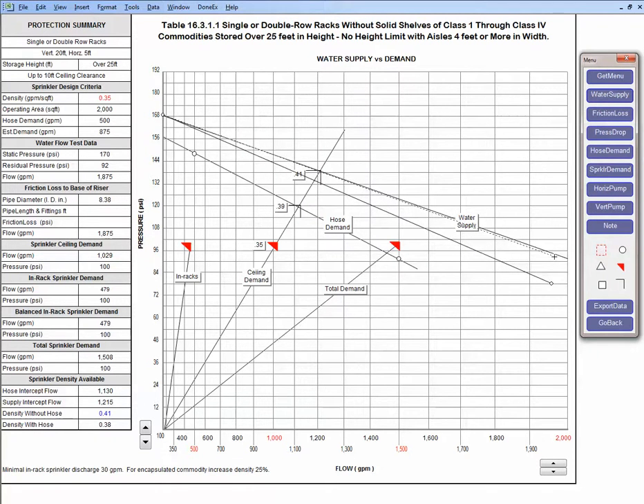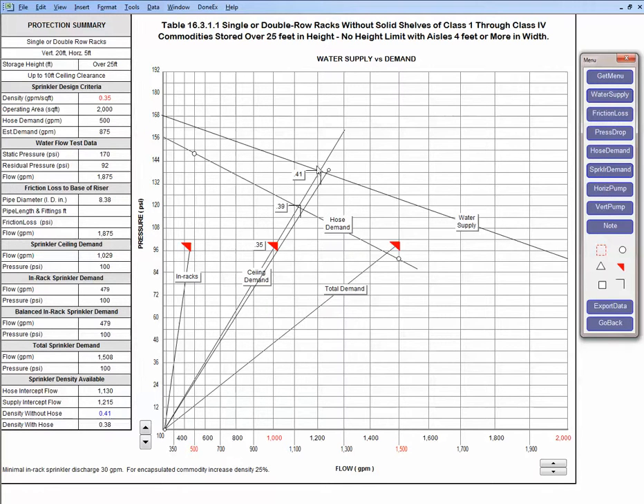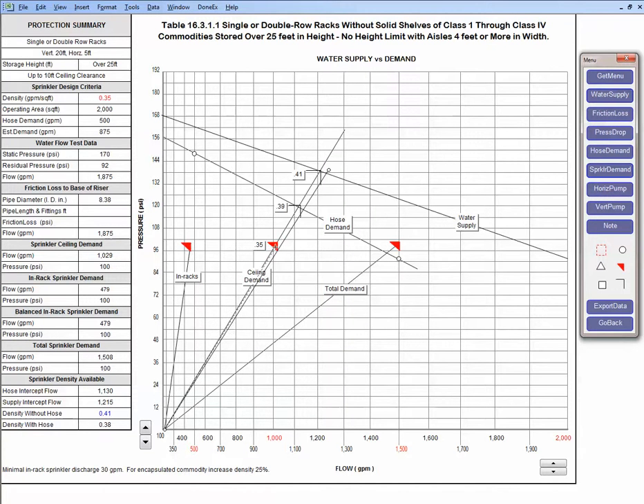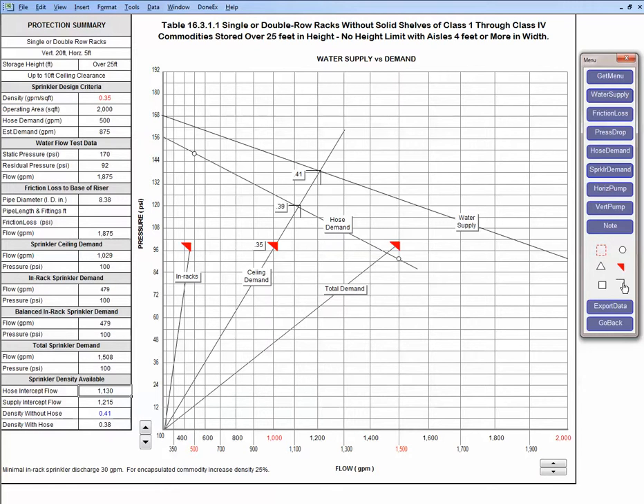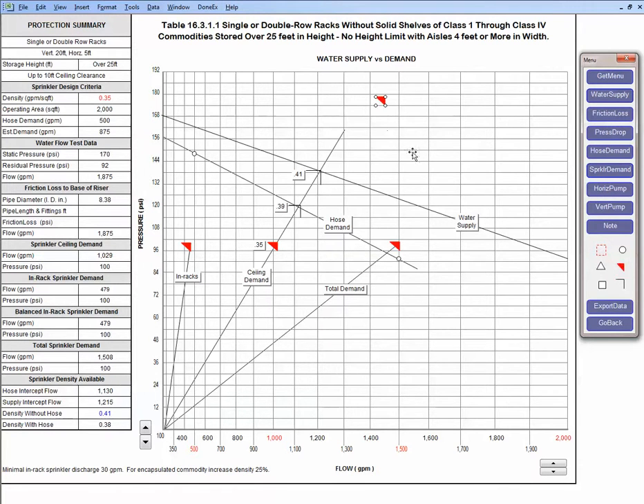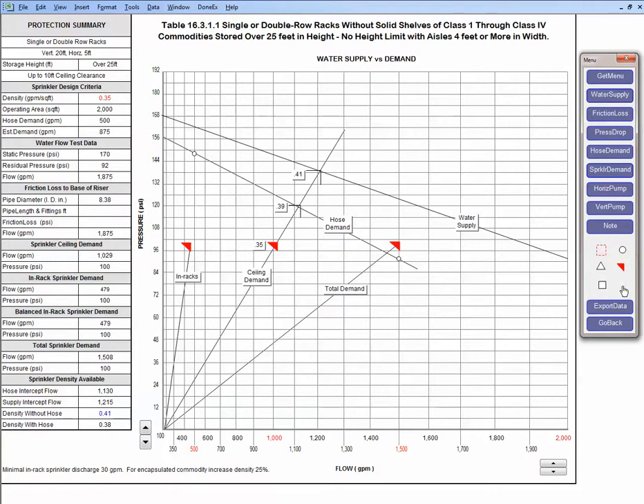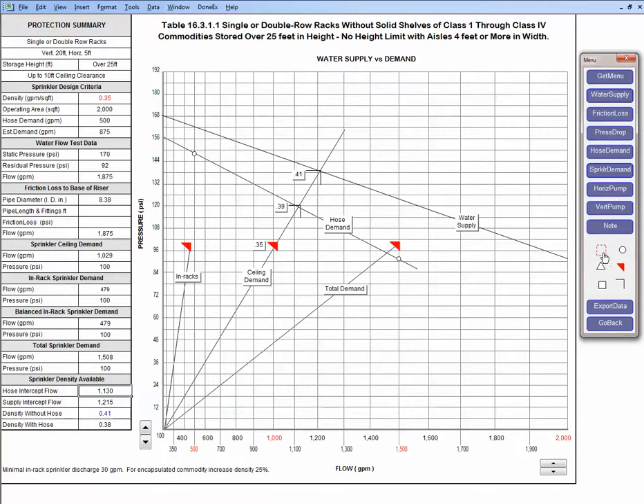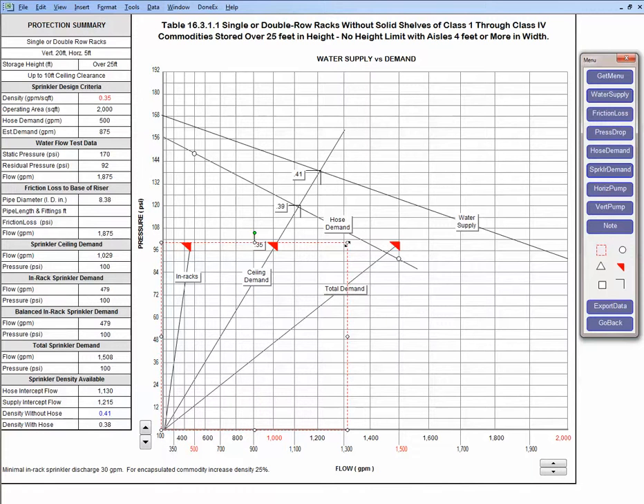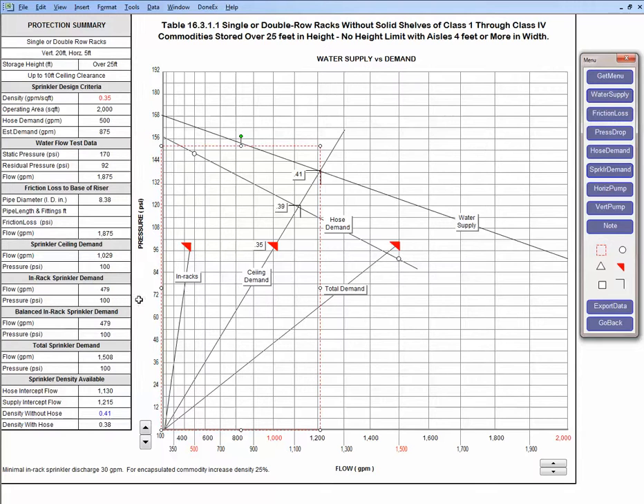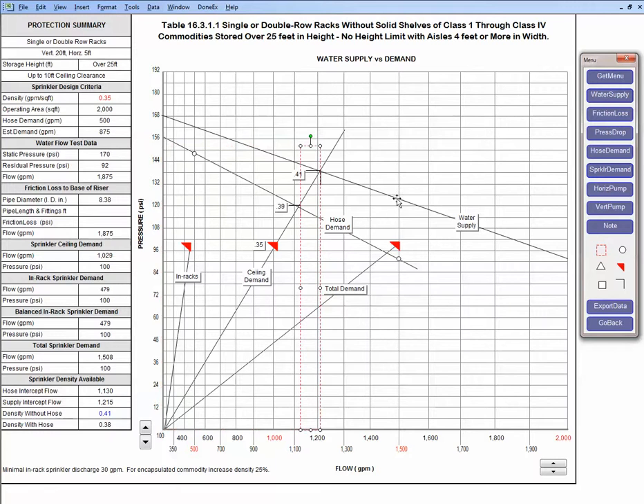If I want to get a water supply line, I click water supply and one drops down, so all I got to do is move it around to my static pressure and then to my residual pressure like so. And I got my water supply. I do the same thing with sprinkler demand line. Once I have it, I click it and put it to where my demand points are. Now I also have little fittings and symbols that I use for this particular case. To show the sprinkler demand I click this red triangle, it drops down and I move it and bring it to the center. I use this open triangle to identify density available with hose and without hose. To do that I also have a guideline which helps me to apply those lines. I put it like so, one side on top of the hose with the water supply intersecting the sprinkler demand, and with the hose demand intersecting your sprinkler demand.